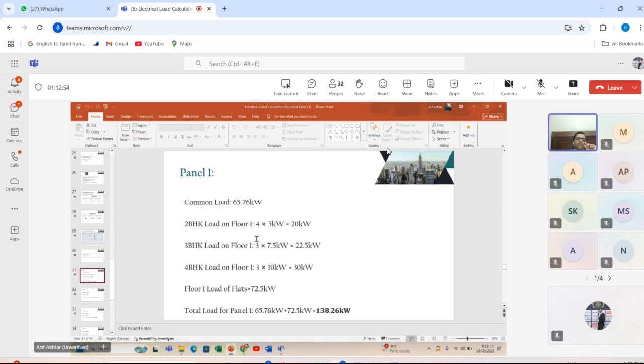Now, panel number 1. For panel 1, we have calculated the common load as 65.76 kilowatt. For 2 BHK on floor 1, we have four flats and each has 5 kilowatt, so we multiply 4 into 5, which is 20 kilowatt. Then for 3 BHK, 3 multiplied by 7.5, 22.5 kilowatt. For 4 BHK, it is 30 kilowatt, and so it goes on. Now the total load for panel 1 is 65.76 kilowatt plus 72.5 kilowatt, which is equal to 138.26 kilowatt. This is the load of panel 1.